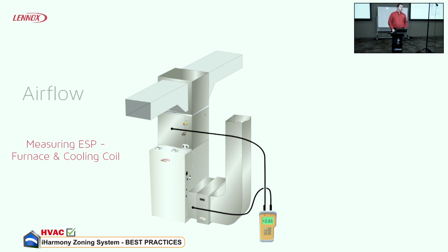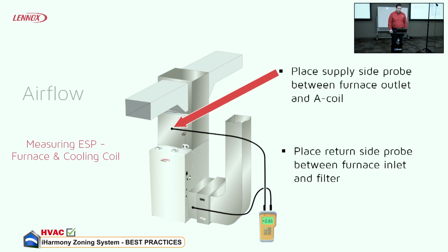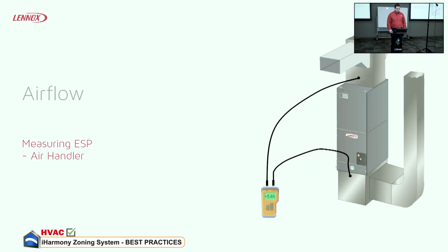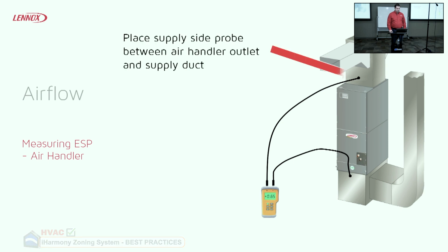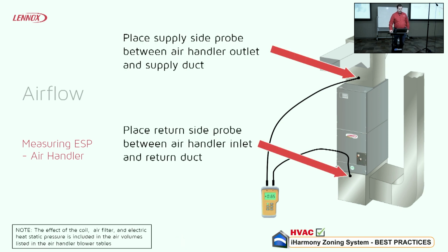What are these furnaces rated on static pressure? Man, now we are asking the proper questions here. Basically, you're looking at 1 inch. I think I've got a slide in here that shows it. On the larger stuff, it's 1 inch. I think like 4 and 5 tons, like 3.5. I think the max is 0.8. It says it there in the spec, but that's an important thing.